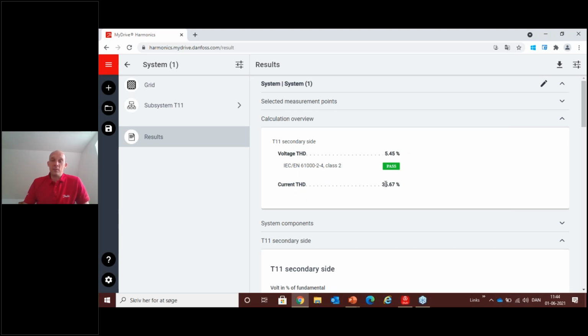You can also see the current distortion is 35%. If you were trying to achieve 5% current distortion in your installation, you would have to put in a lot of mitigation equipment. It would probably reduce the voltage distortion quite a bit, but it will not give you a more reliable and safe installation. You will simply add a lot of equipment that costs a ton of money without really giving you any benefits. That's why the voltage distortion is the important value to look at. Don't look too much at the current. It's the voltage distortion that is the important part of the installation.